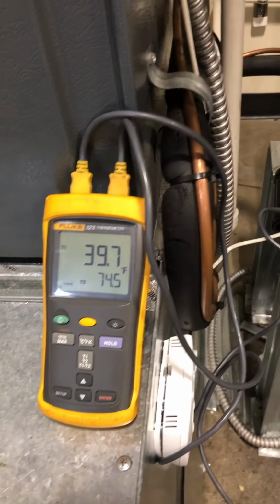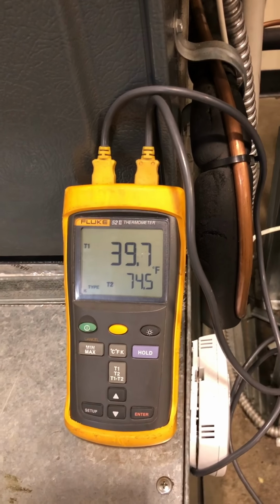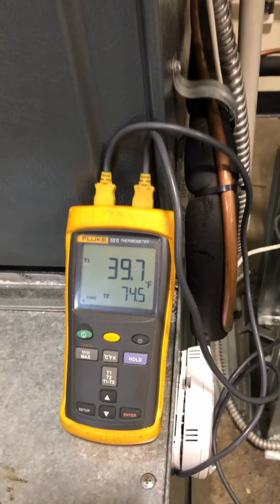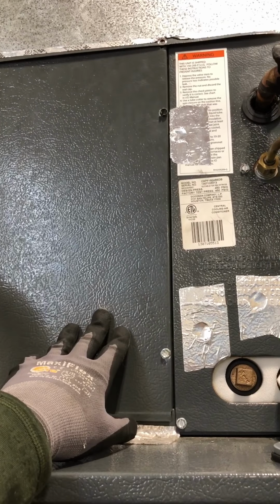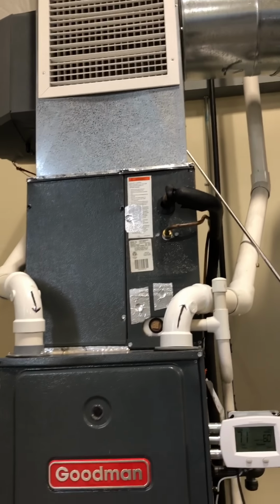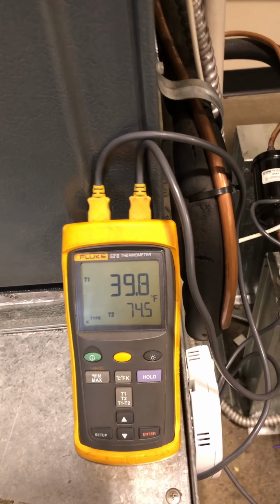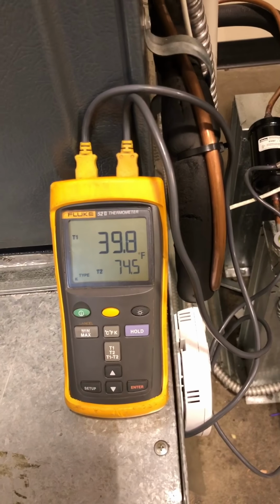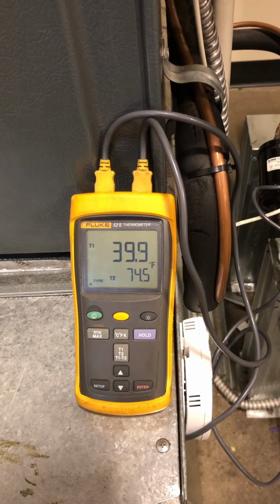So right now, based on those 2, I'm thinking that this unit might be just slightly overcharged. We don't have a whole lot of superheat. We want to be picking up heat. We want to be picking up some heat on this coil in order for us to be cooling the structure down like we're supposed to. So right now the red flag to me, and my meter just turned off, the red flag to me is that low superheat. We have 2 degrees superheat. That's pretty low. Superheat, subcooling, first 2 things you check.